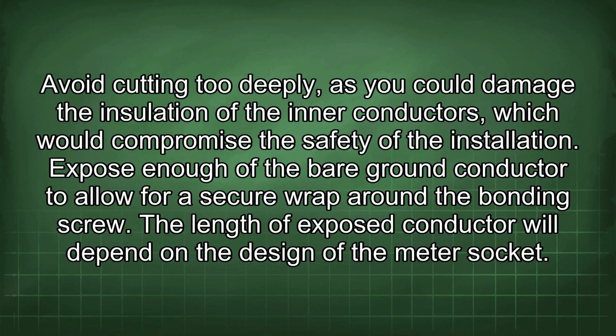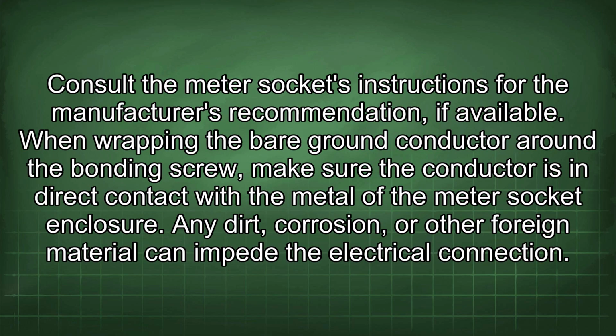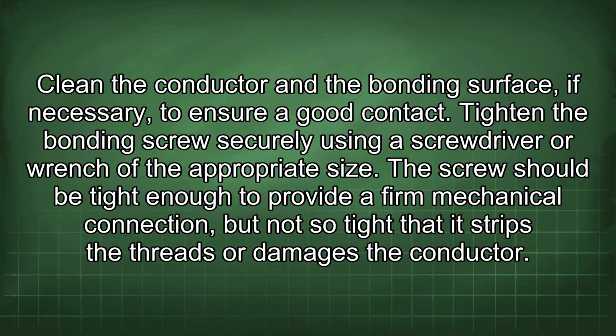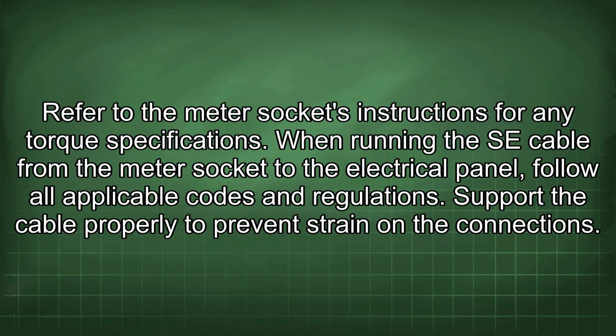The length of exposed conductor will depend on the design of the meter socket. Consult the meter socket's instructions for the manufacturer's recommendation, if available. When wrapping the bare ground conductor around the bonding screw, make sure the conductor is in direct contact with the metal of the meter socket enclosure. Any dirt, corrosion, or other foreign material can impede the electrical connection. Clean the conductor and the bonding surface, if necessary, to ensure good contact. Tighten the bonding screw securely using a screwdriver or wrench of the appropriate size. The screw should be tight enough to provide a firm mechanical connection, but not so tight that it strips the threads or damages the conductor.